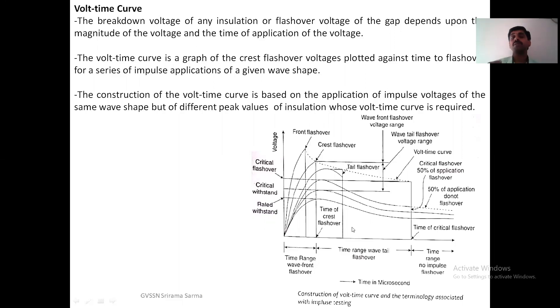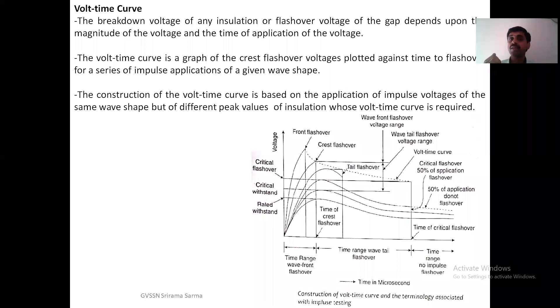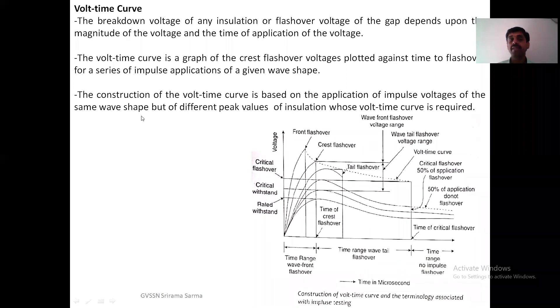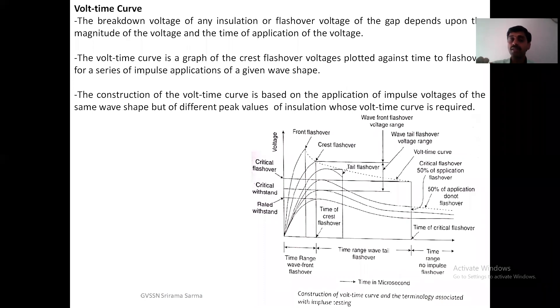We apply different voltages of different magnitudes but with the same wave shape. Taking one impulse wave shape, the same wave shape is applied at different magnitudes, and we test the insulation to see when it flashes over and when it withstands. Construction of the volt-time curve is based on the application of impulse voltages of the same wave shape but different peak values to the insulation whose volt-time curve is required. These volt-time curves of the equipment should match and correlate with the volt-time curves of the protective device — then one device can protect the entire equipment. That is called insulation coordination.